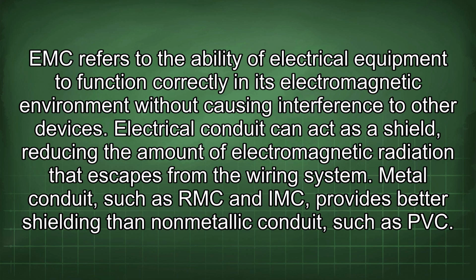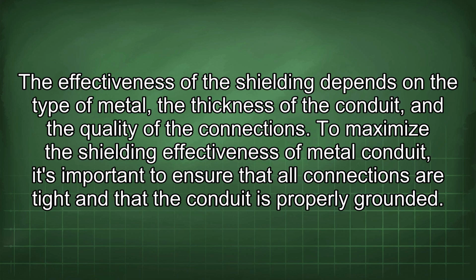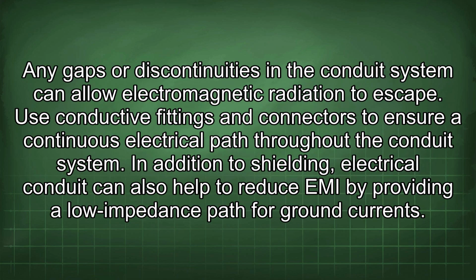Electrical conduit can act as a shield, reducing the amount of electromagnetic radiation that escapes from the wiring system. Metal conduit, such as RMC and IMC, provides better shielding than non-metallic conduit, such as PVC. The effectiveness of the shielding depends on the type of metal, the thickness of the conduit, and the quality of the connections. To maximize the shielding effectiveness of metal conduit, it's important to ensure that all connections are tight and that the conduit is properly grounded. Any gaps or discontinuities in the conduit system can allow electromagnetic radiation to escape. Use conductive fittings and connectors to ensure a continuous electrical path throughout the conduit system.